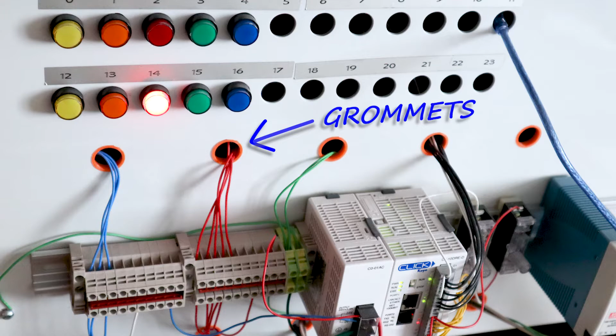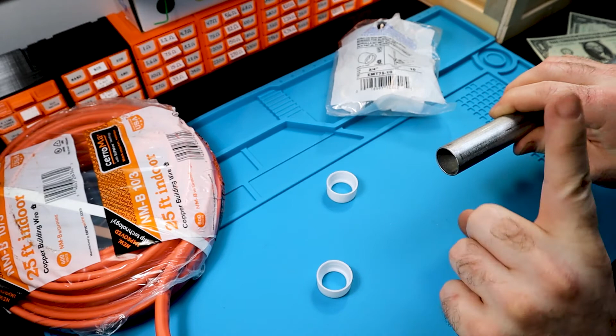Tip number 12: use grommets and bushings when routing wire into panels or through conduit. I'll put up some pictures to show what I mean, and address this later when we get to that topic. If you don't use grommets or bushings, over time, especially routing wiring to a motor, sharp edges can rub into your insulation and eventually short out the wires.